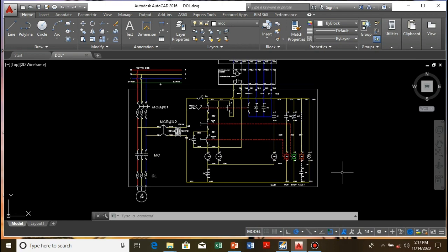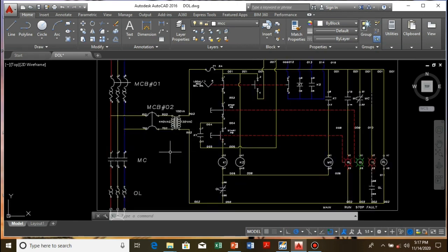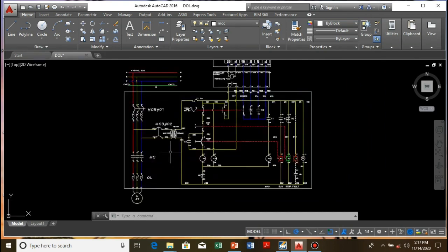In spite of its advantages, simple equipment, high starting torque, fast start, low cost, direct online starting is only suitable when the power of the motor is low compared to that of the mains, which limits interference from inrush current. The machine to drive does not need to speed up gradually or have a damping device to limit the shock of starting. The starting torque can be high without affecting machine operation or the load that is driven. So this direct online is applicable to industrial power systems, including some of the commercial.